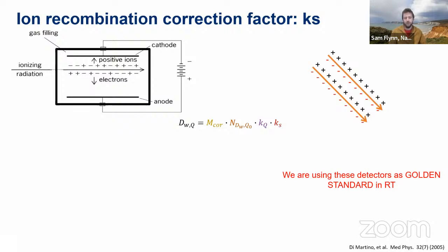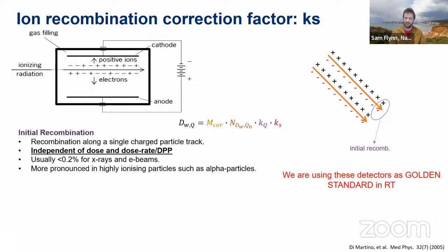There are two forms of ion recombination. You have initial recombination, which is when the ion pairs that are created will join back with each other as part of the same track, and that is particle dependent. So that depends on whether you're using a carbon beam or low energy X-rays, and it's pretty consistent. It's much more prominent for high energy, high LET particles, such as alpha. But for the most part, it's not as much of a consequence.